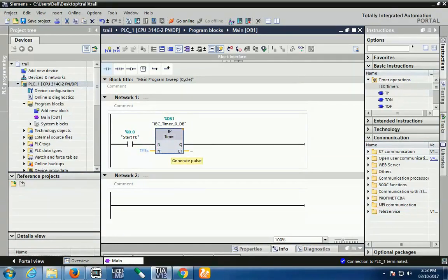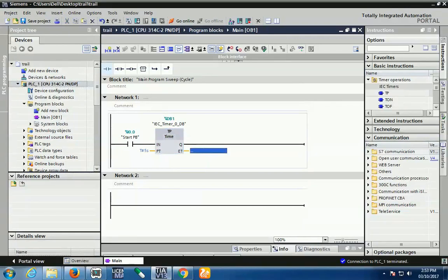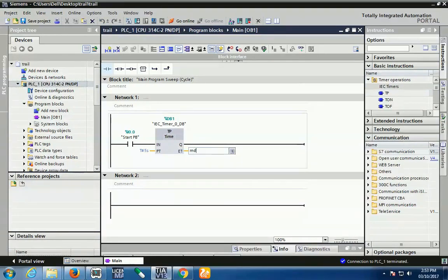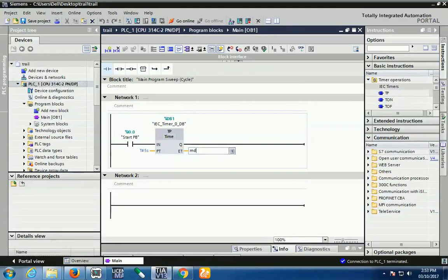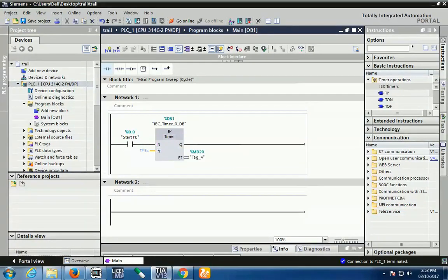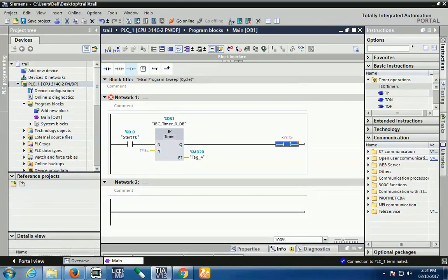This shows how much time your timer is running, the current time. If you want to display current time in HMI and SCADA, we use double word because ET basically uses time data type, and for time data type we use the double word. So here I mention MD20 and here I configured one coil as the output.